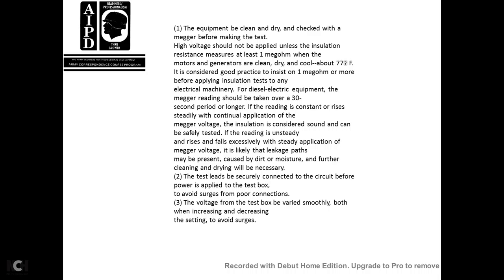When the motors or generators are clean and dry and cool, at about 77 degrees Fahrenheit, it's considered good practice to insist on 1 megohm or more before applying the insulation testing in the electrical machinery. For diesel-electric equipment, the megger reading should be taken at a 30 second period or longer.